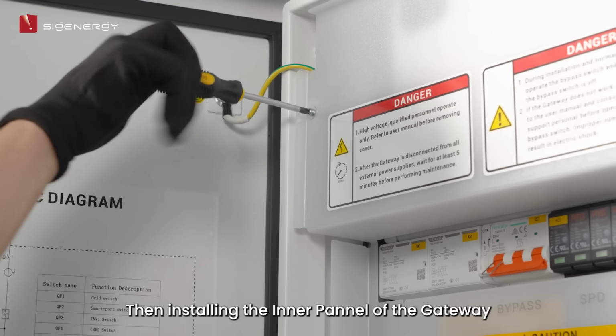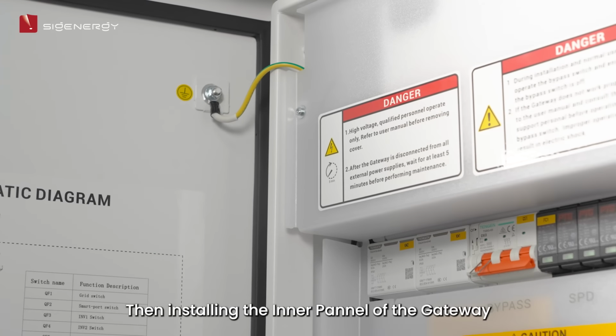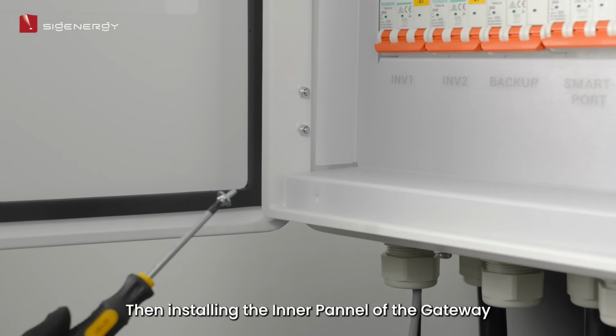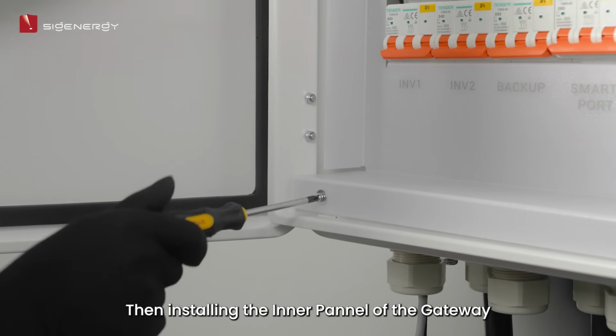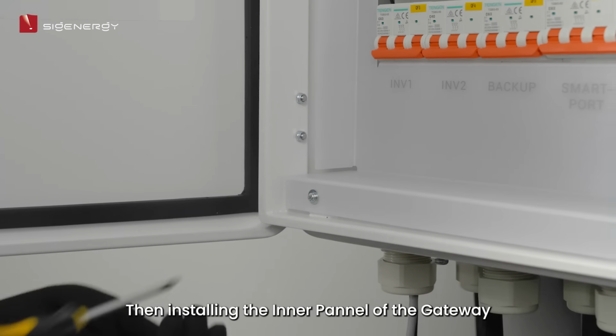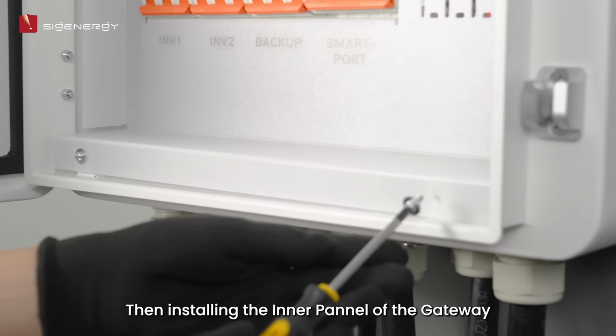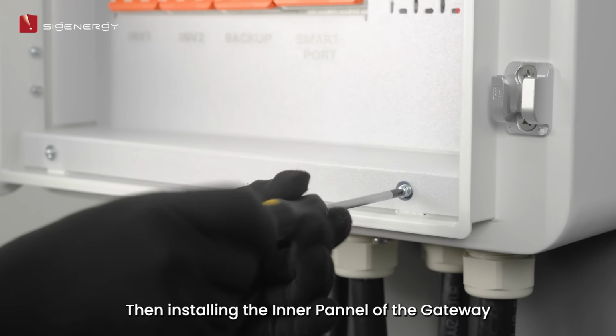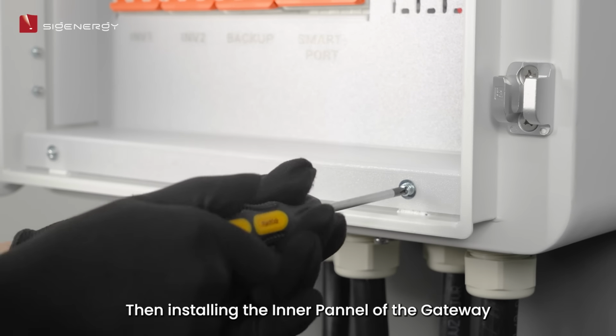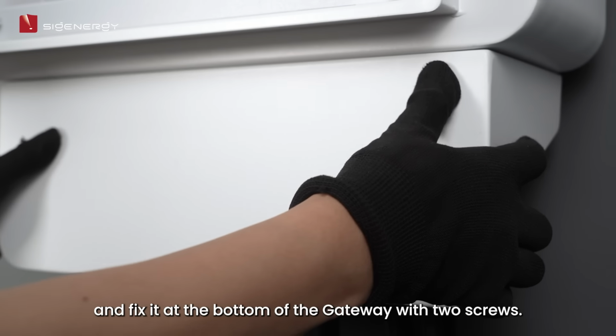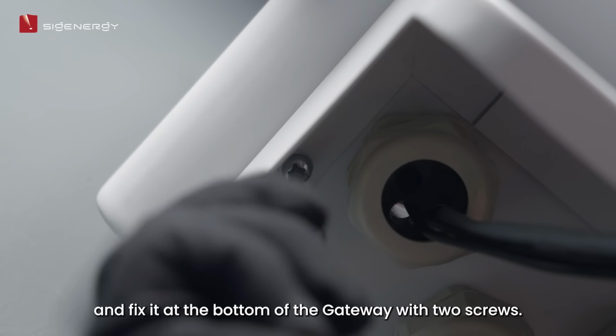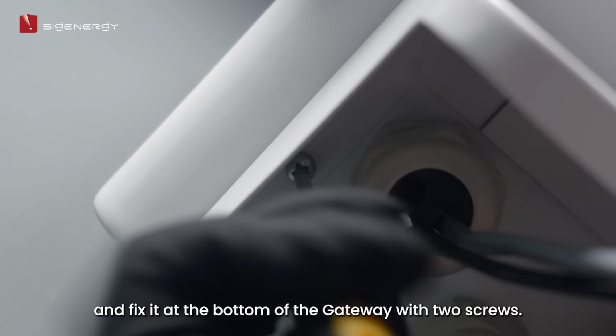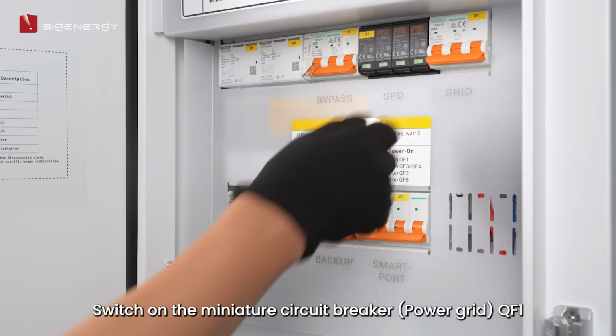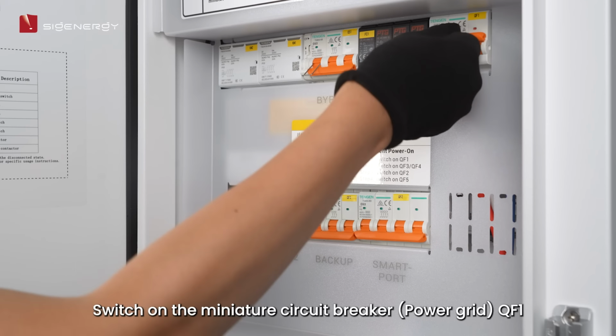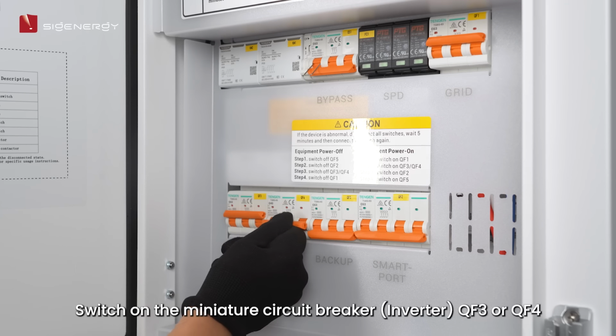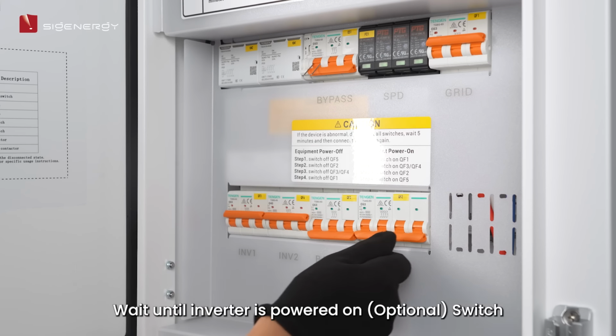Then installing the inner panel of the gateway. Install the decorative cover and fix it at the bottom of the gateway with 2 screws. Turn on the front switch of the equipment. Switch on the miniature circuit breaker, power grid, QF1. Switch on the miniature circuit breaker, inverter, QF3 or QF4. Wait until inverter is powered on.